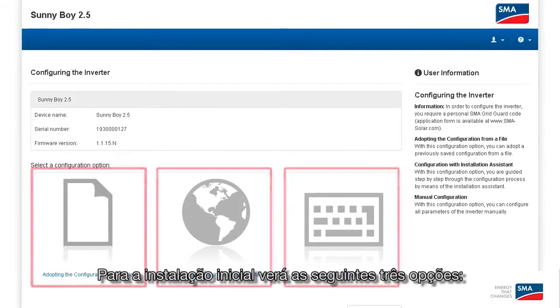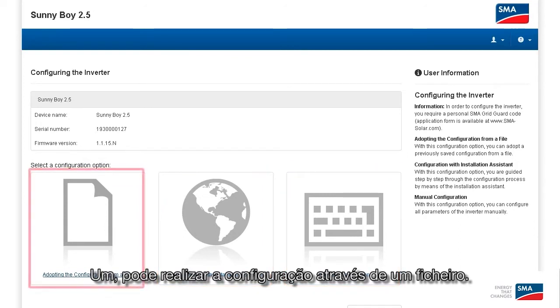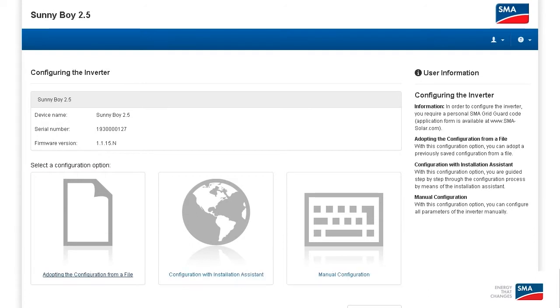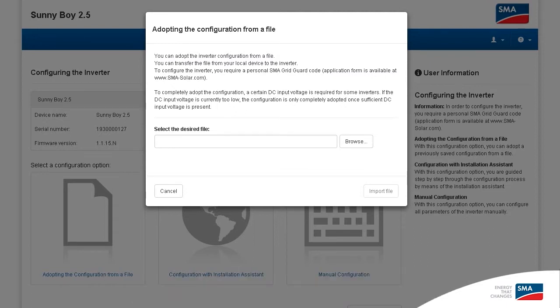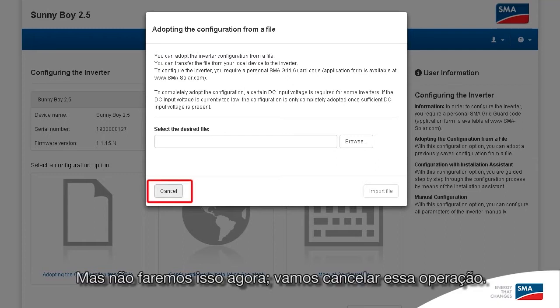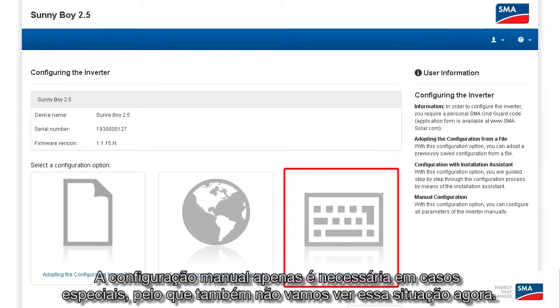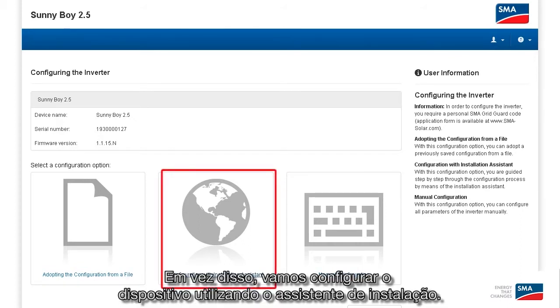For the initial installation, you'll see the following three options. One, you can perform the configuration via a data file. I would do that if you plan to install several inverters of the same type, because you can just store the same installation settings, select the file and import it. But we're not going to do this now. Instead, we simply go here to cancel. Manual configuration is really only necessary in special cases, so we're not going to go through that now either. Instead, we're going to configure the device using the installation assistant.